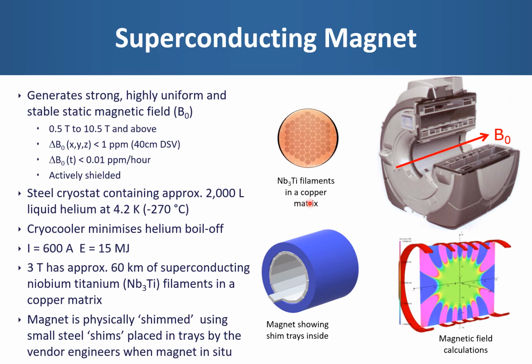To ensure that the uniformity of the magnetic field is as good as possible when the magnet is installed, the magnet is physically shimmed by the engineer after it has been ramped to the desired field, so that the effects of any steel within the walls or girders above or below the magnet can be taken into consideration. So inside the room temperature bore of the magnet, there will be a large number of these shim trays, where shims, which are effectively just small steel pieces, are put into appropriate locations in the shim trays. A separate system is then used to iteratively plot the field in 3 dimensions and calculate the amount and position of the shims inside these trays.